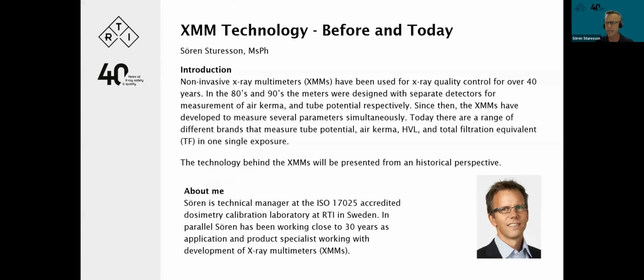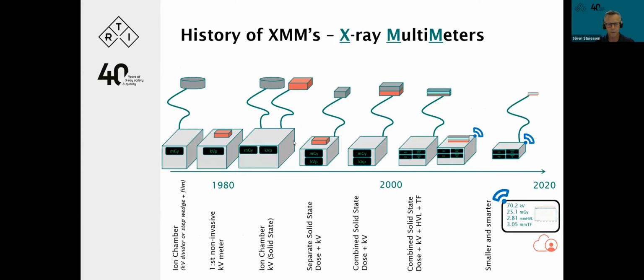Non-invasive multimeters, XMMs, have been in the market for about 40 years, depending on what we mean with an X-ray multimeter, but we many times say that it's at least something that measures kVp or kV non-invasively together with other parameters. If we start 40 years ago, or 40 years plus, that was when the first non-invasive kV meters came into the market. At that time, it was a device that measured kV, maybe time. You had to have another device to measure dose, and that was typically an ion chamber.